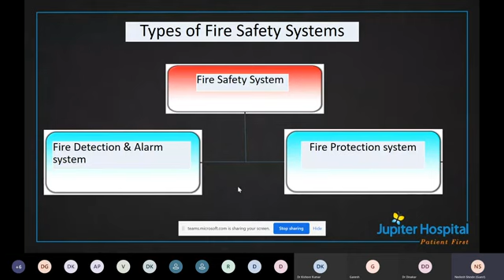Whenever we talk about a fire alarm system, there are two types: conventional and addressable. In the conventional type, used in earlier times and still in many places, one zone is considered, and within that zone there are a lot of smoke detectors, maybe covering 400 to 500 square feet or more.